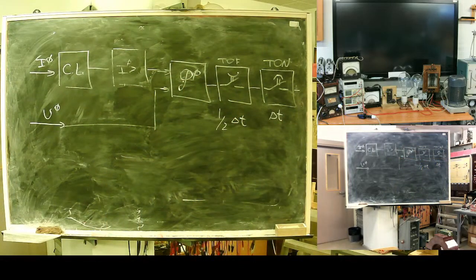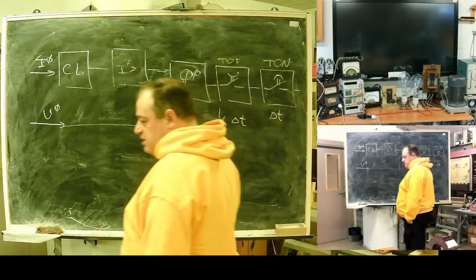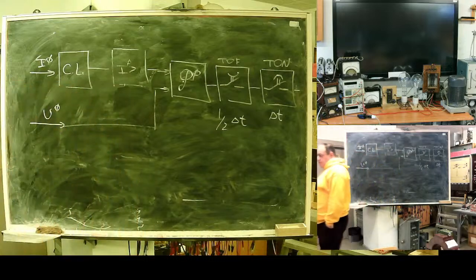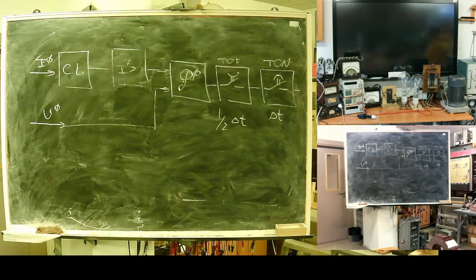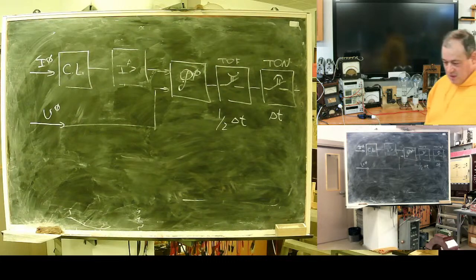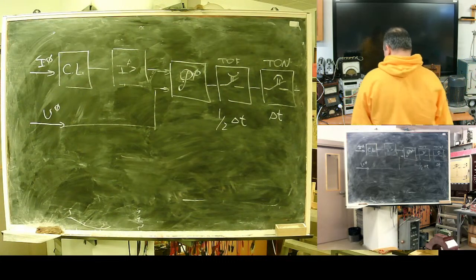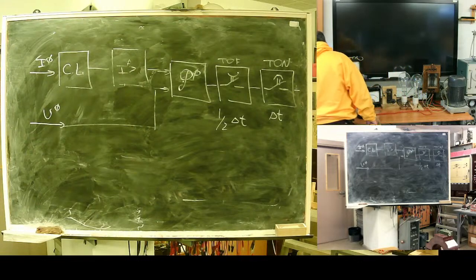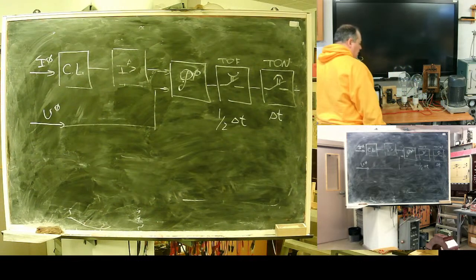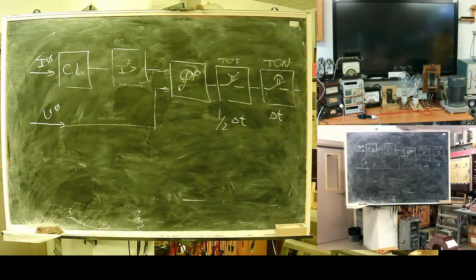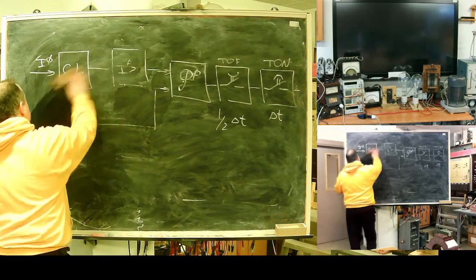When people started to think about reliability of network, reliability of supply, what can be done? I need to continue operation during a fault. If fault current is small, I can continue. If fault current reach dangerous levels, something should be done. And technique called compensated network was introduced.